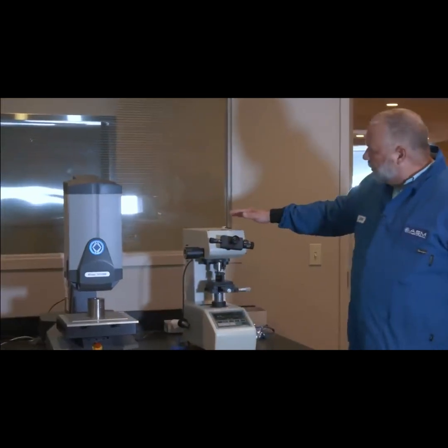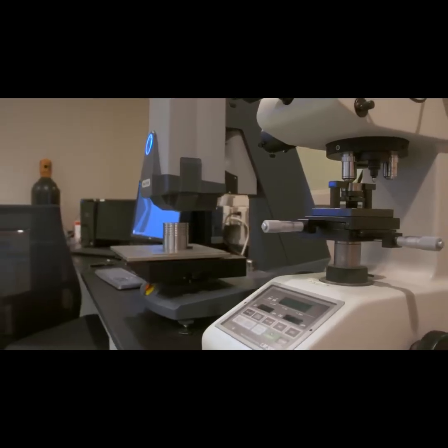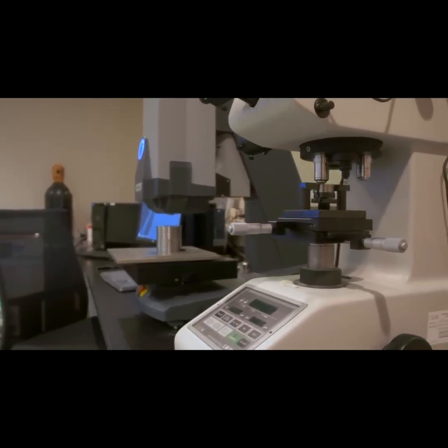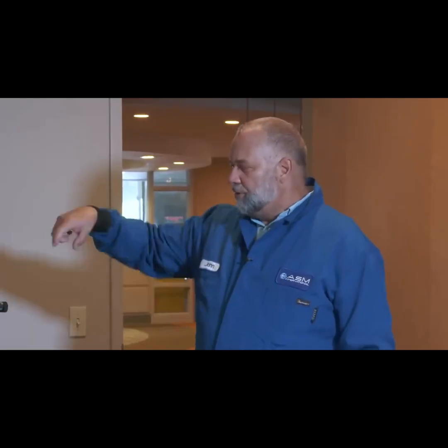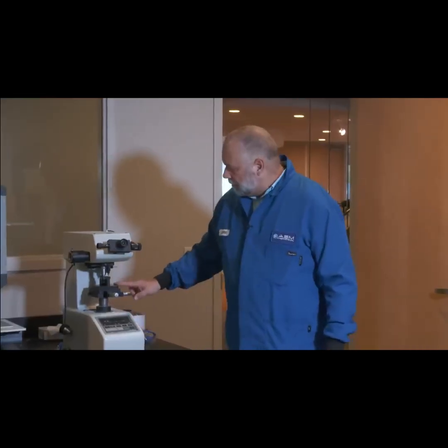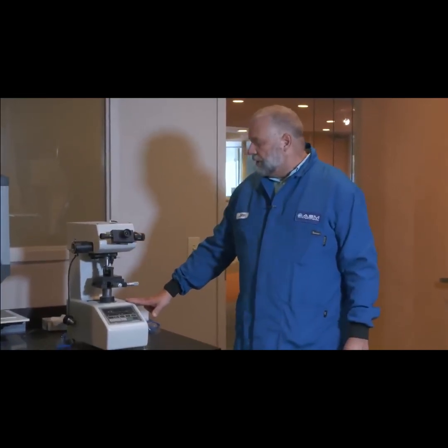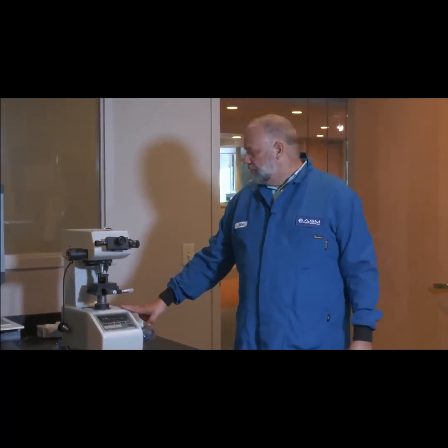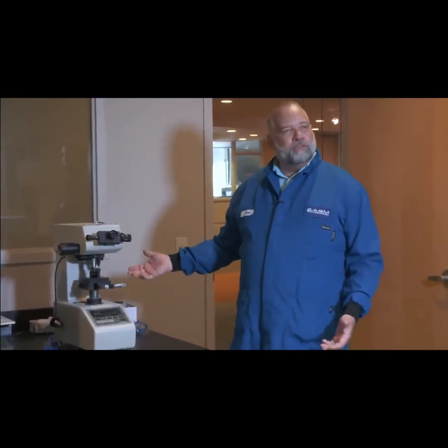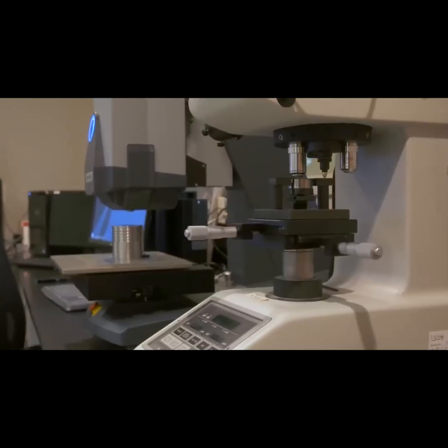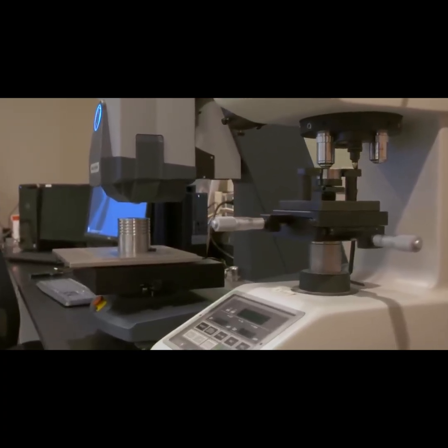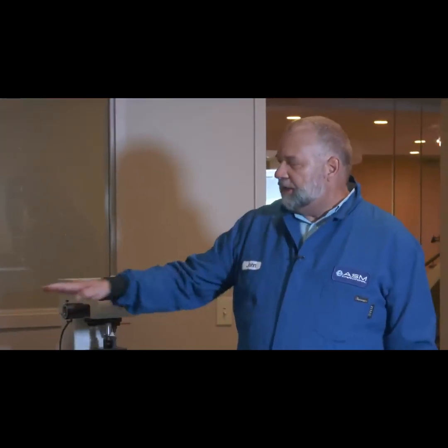And this is a micro hardness tester that is very manual. You measure in the eyepiece the shape of the dimensions, and normally one or two diagonals, and then you bring it down, and then you have to dwell for 10 seconds or so. So every indentation takes about 20 to 30 seconds. Now that you have automation of a fully motorized stage, a camera that measures the indentation, and a stage that can lay down predefined patterns, you can do hundreds of indentations.